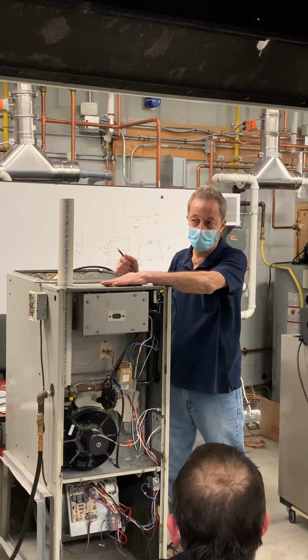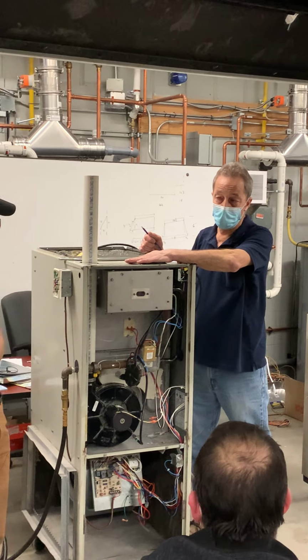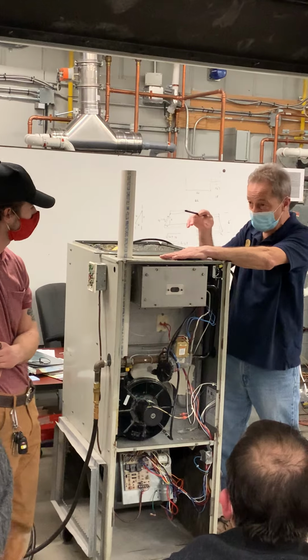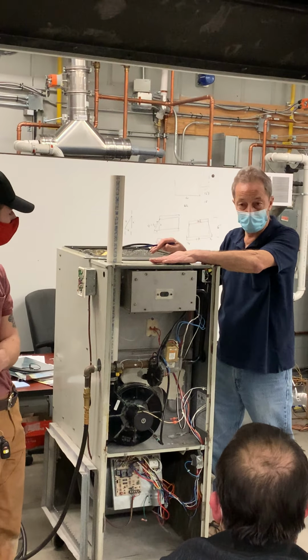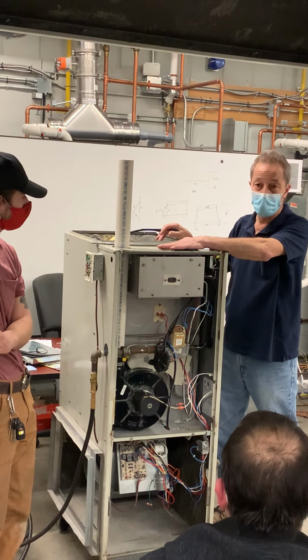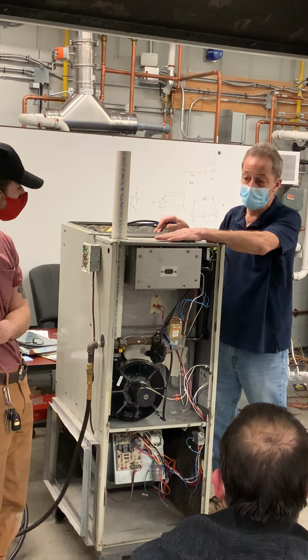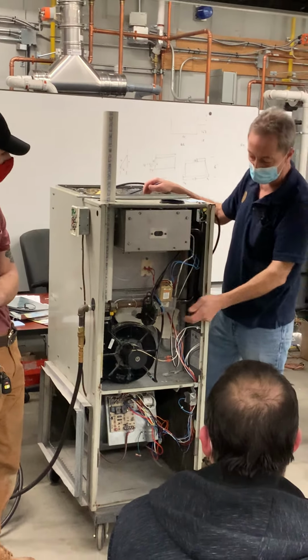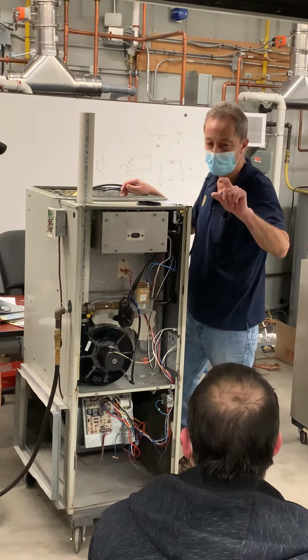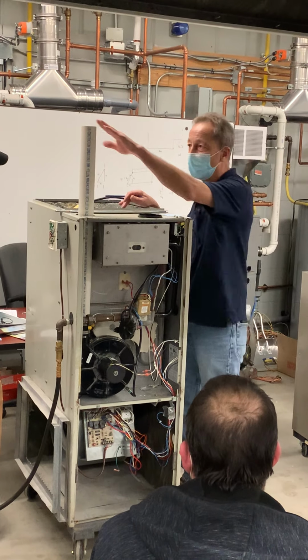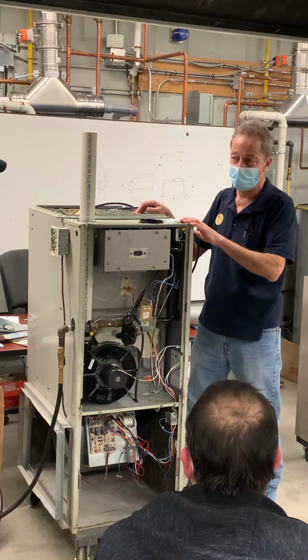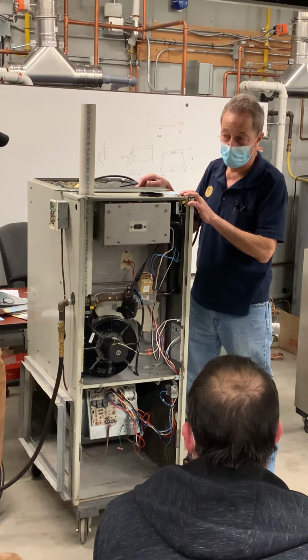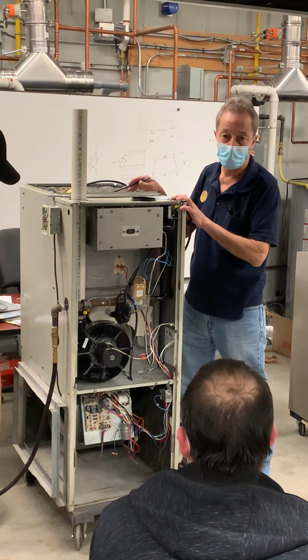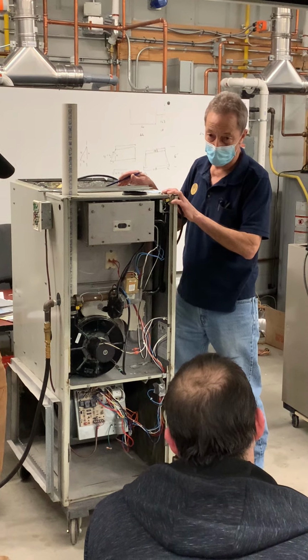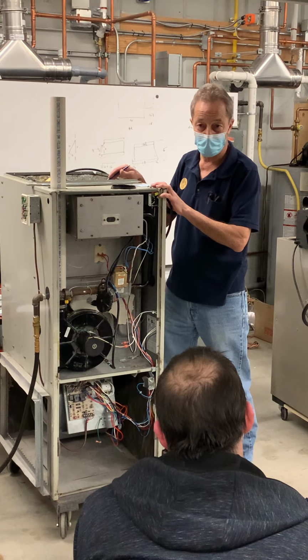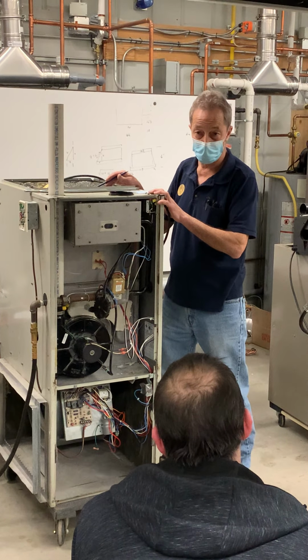Would it increase or decrease? They get more negative, if I block the intake. I agree totally. And I lose the differential, because the negative pressure here will get closer to the negative pressure here, so I don't have sufficient differential. If I block the exhaust, what happens to the pressure? More negative or more positive? More positive. Yep, it's going to get more positive, so it'll get closer to zero.